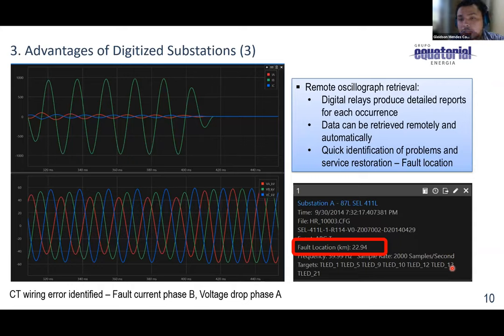One of the pieces of information that we can retrieve is oscillography, which is really important for fault location. And once the fault location is identified, we can restore the service as quickly as possible, because we act where the problem is located. We don't have to search the whole line to see where the problem is. And all of this we can retrieve automatically.